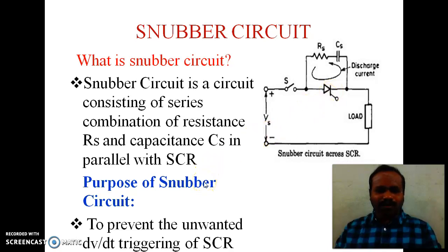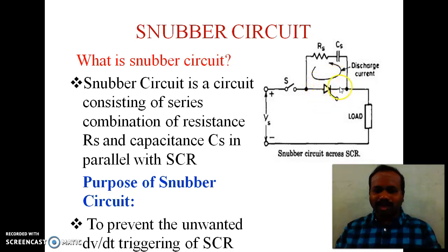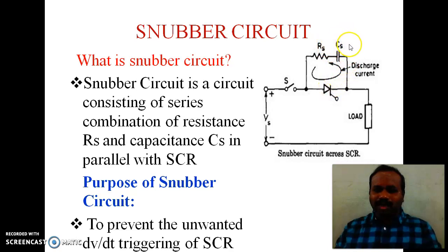The purpose of the snubber circuit is to prevent the unwanted dV/dt triggering of the SCR. Whenever the supply is connected to the thyristor, if the rate of rise of voltage increases, then the thyristor will get an unwanted trigger. In order to avoid this malfunction, we must control the dV/dt which appears across the thyristor. We connect a capacitor in parallel with the thyristor because the capacitor does not allow any sudden change of voltage — it will allow only a slow increase of voltage.